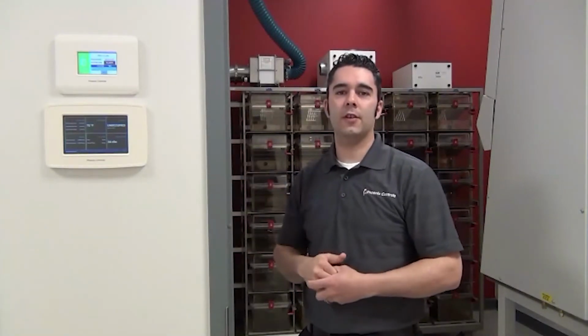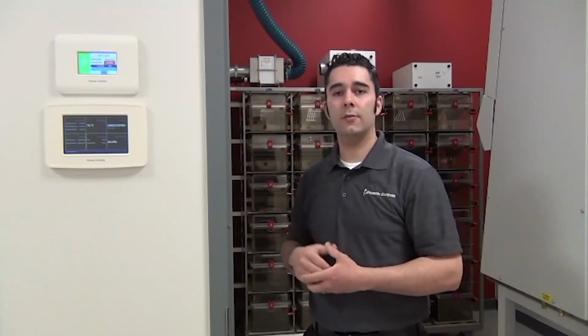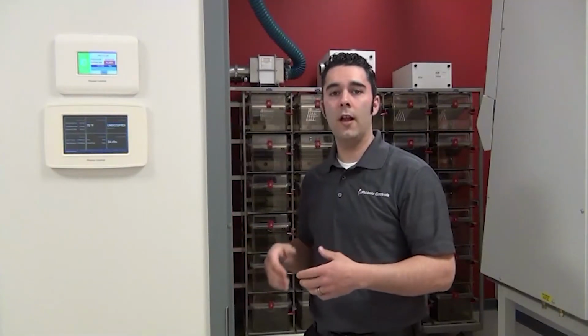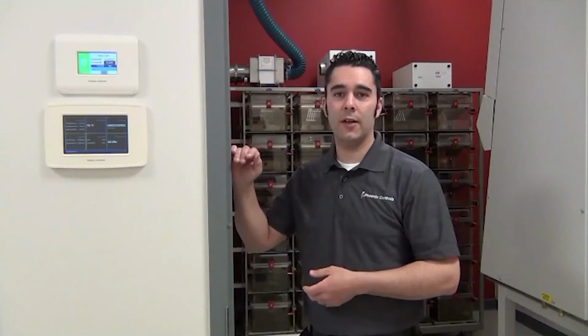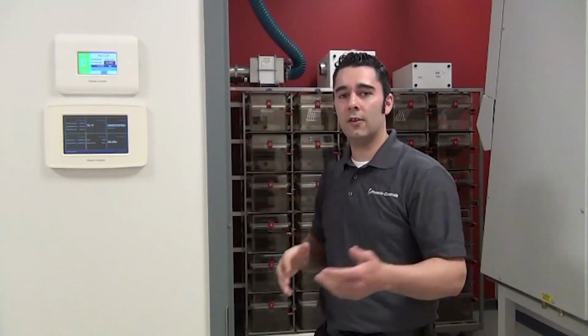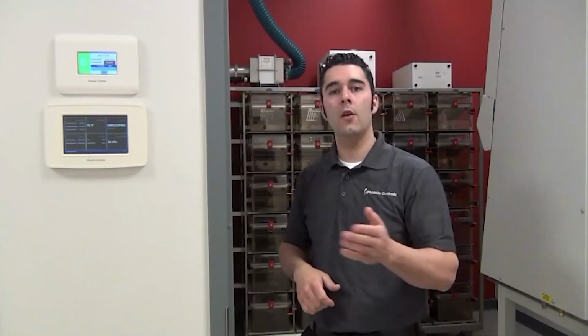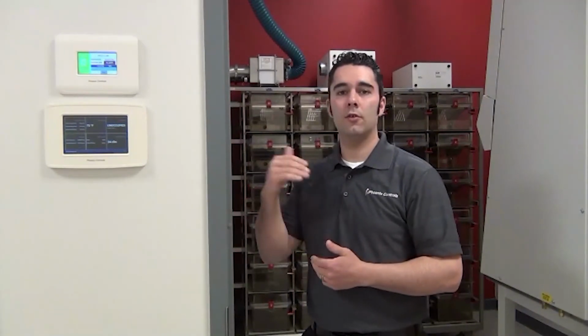Another feature of the progressive offset control is that this door actually has a door switch in the frame. That's going to serve two purposes. What it's going to do is when I open the door, I'm going to freeze the output to the PID loop, therefore I won't wind out to the extent of my PID. It will also introduce an alternate higher offset. So I know that when the doors open, I'm not going to be able to maintain my 0.03 differential pressure across the door. However, I can go from 175 CFM negative up to 350 CFM negative, and at least guarantee that I have directional airflow as long as the door is open. When I close that door, it'll notify the PID loop to pick up where it left off, and it'll send my offset back to its previous set point. So within 1 to 2 seconds of the door closing, you're right back in control where you were before, so you don't have spikes in your pressure while the door's opening and closing.